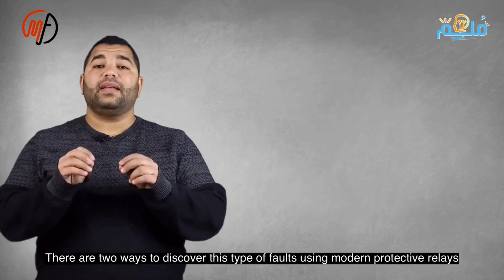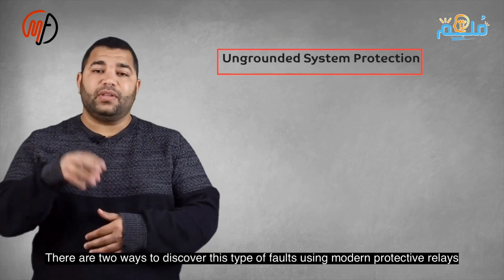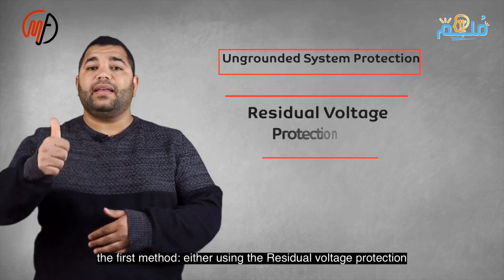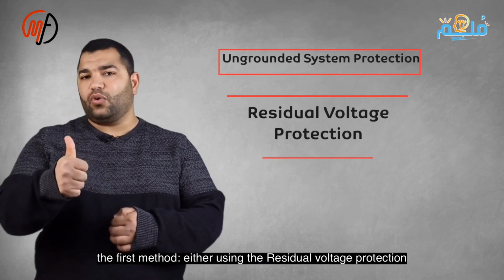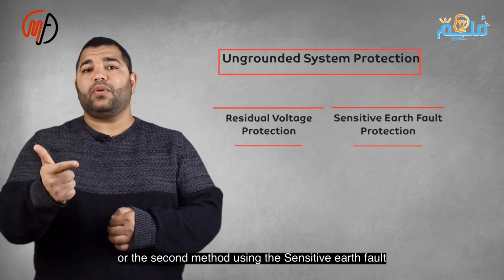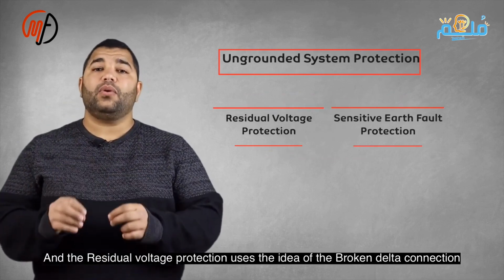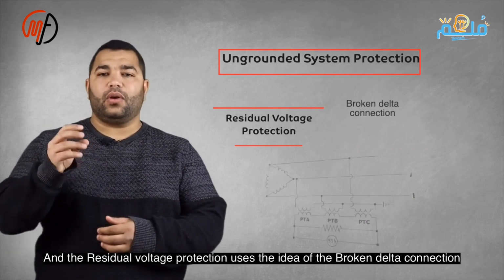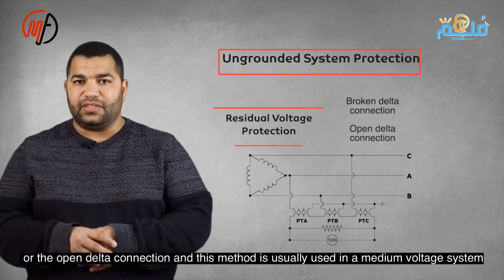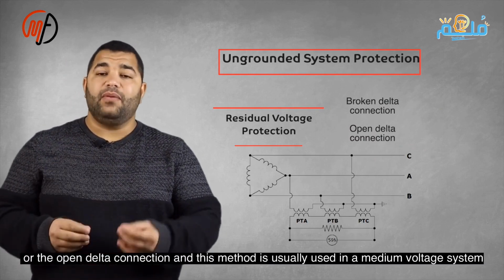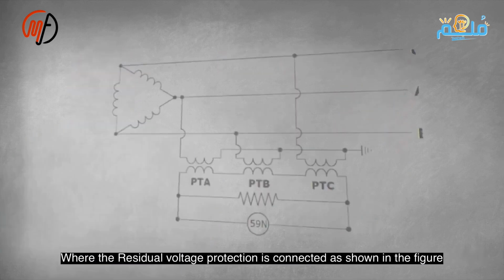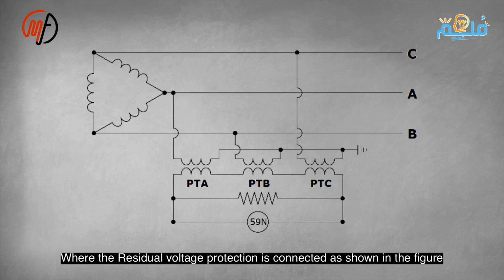There are two methods to detect this type of fault using modern protection devices. The first method is using residual voltage protection, and the second method is using sensitive ground fault. Residual voltage protection uses the concept of broken delta connection or open delta connection, and this method is usually used in medium voltage systems where the residual voltage protection is connected as shown in the diagram.